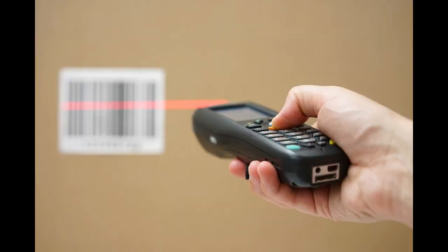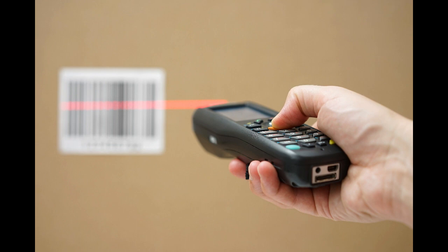To ensure traceability, organisations need to uniquely identify monitoring and measuring equipment. This identification can be achieved through methods such as labeling, tagging or serial numbering. The identification should enable the equipment to be linked to the calibration and maintenance records, facilitating traceability and accountability.